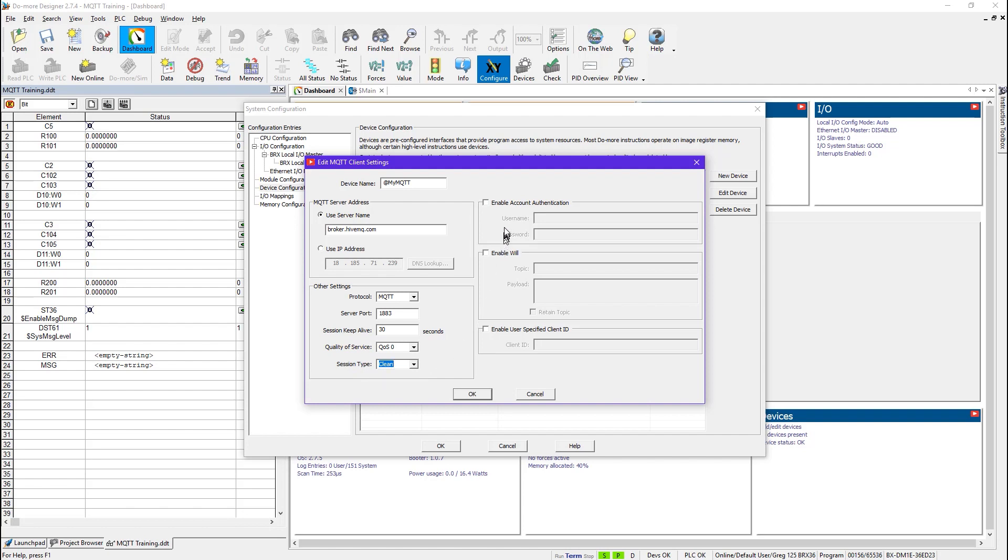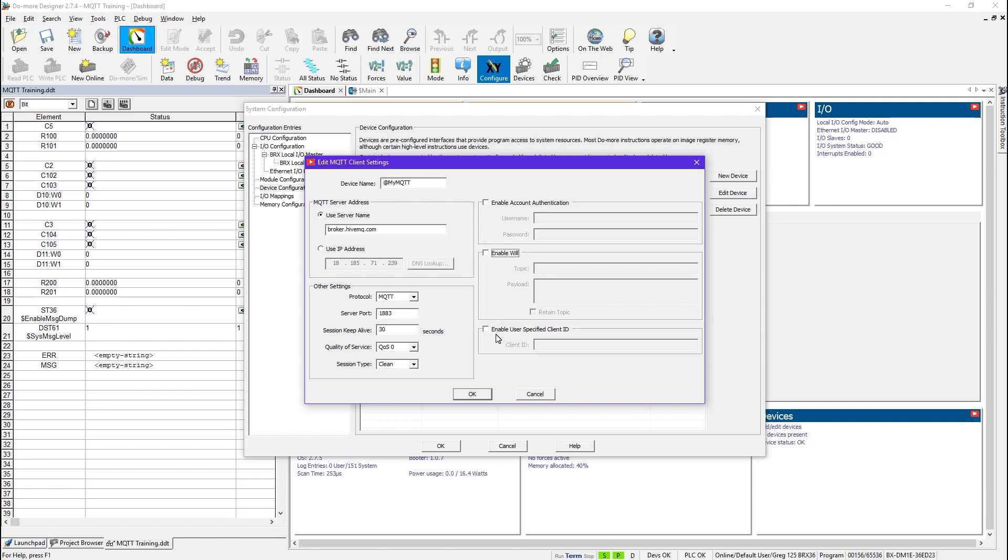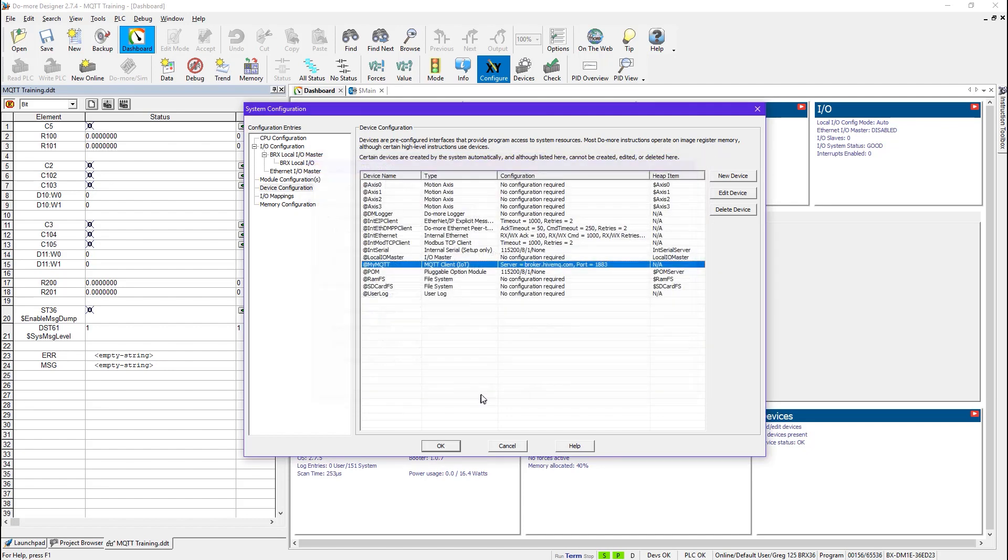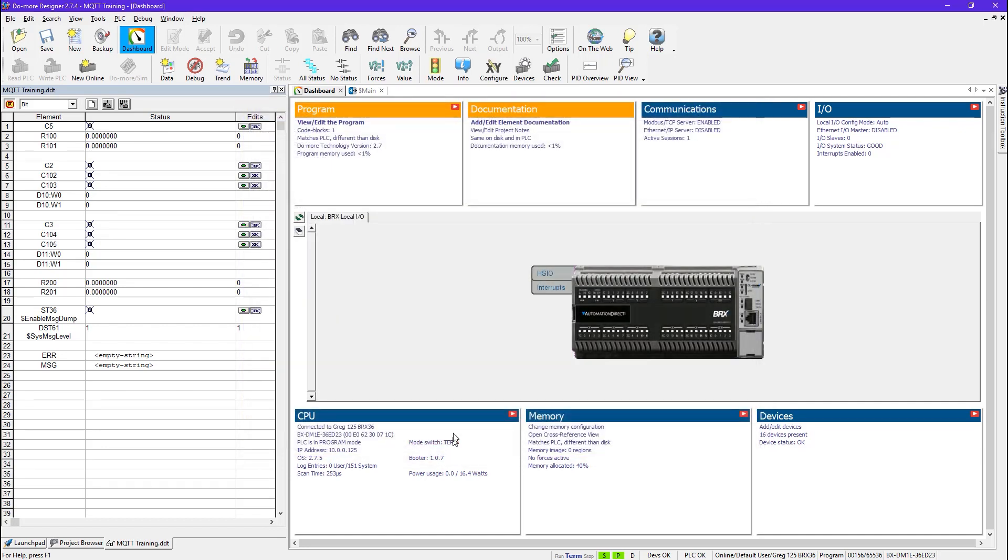And then here, some MQTT brokers require a login before you can use them. So here's where I would pick that and set it. Mine doesn't require that. This is the last will and testament where I would give that a name and what the data is and whether or not to retain it. And this is the enable user-specified client ID. This is a 64-byte ID that's unique for each client that connects to the MQTT broker. Now the BRX PLC will create one for you using its MAC address. But you can assign your own if you wanted to by clicking this. And then of course, I would OK out of these just like so. And I would also write that down to the PLC.